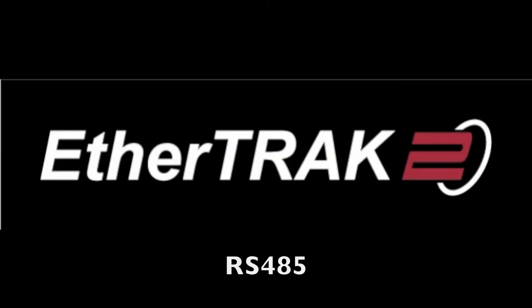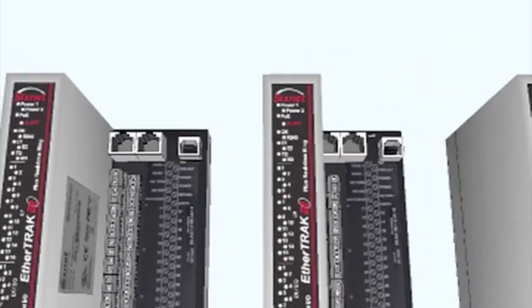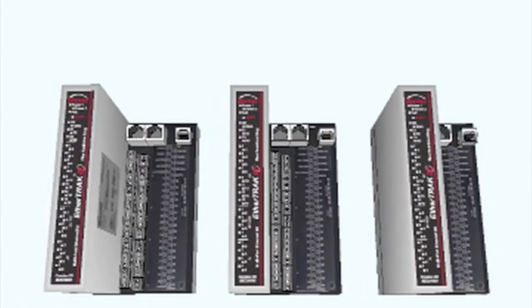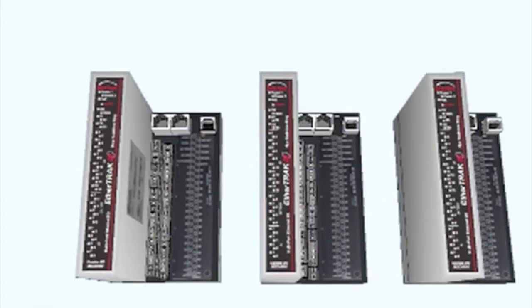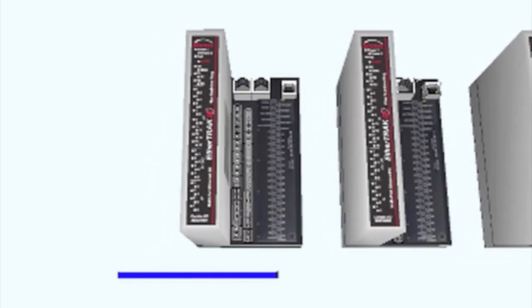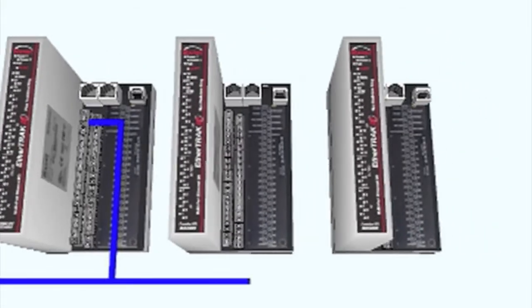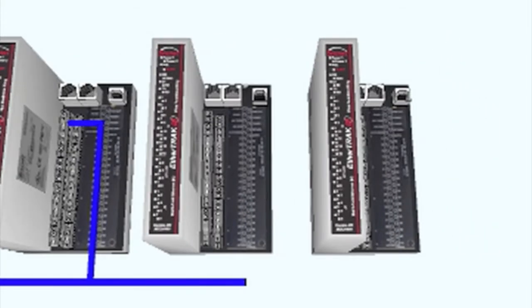The fourth option is to use the two-wire RS-485 serial port. These ports can be daisy-chained together. In this configuration, RS-485 communication standard is used for long wire lengths. The advantage to this topology is that the communication is carried through the wiring only, so any module may be unplugged and communication will remain intact to the rest of the network.